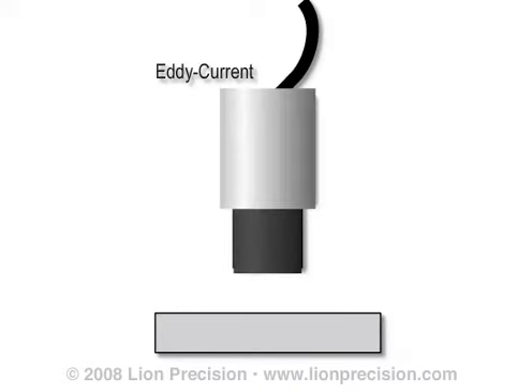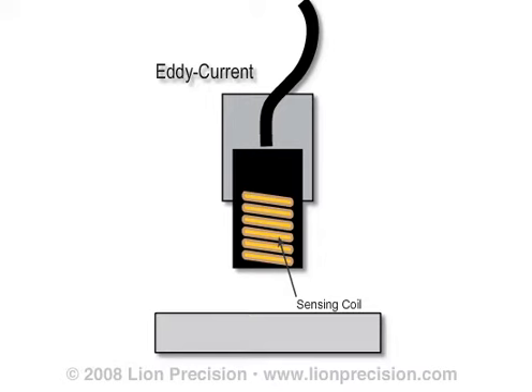The primary functional piece of an eddy current probe is the sensing coil. This is a coil of wire near the end of the probe. Alternating current is passed through the coil, which creates an alternating magnetic field. This field is used to sense the distance to the target. The coil is encapsulated in plastic and epoxy and installed in a stainless steel housing. The magnetic field of an eddy current sensor is not as easily focused as the electric field of a capacitive sensor, so the epoxy-covered coil extends from the steel housing to allow the full sensing field to engage the target.